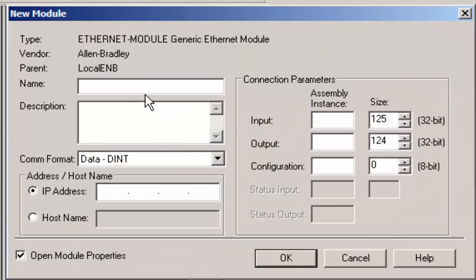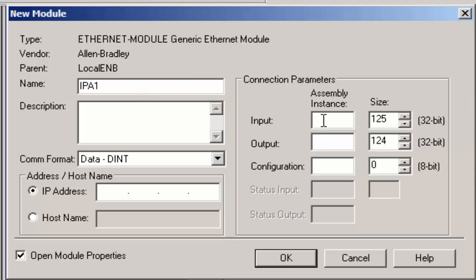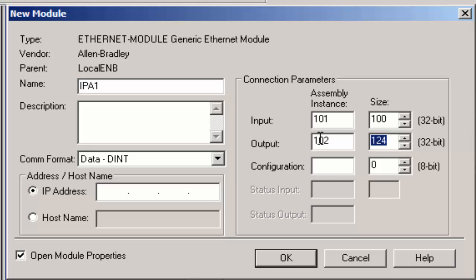And then you want to name the IPA module. So I'm just going to name this IPA1. You could have multiple IPA drives. The input needs to be 101, and then the size is fixed at 100, 32 bits. And then the outs are 102, and then the configuration is 3.